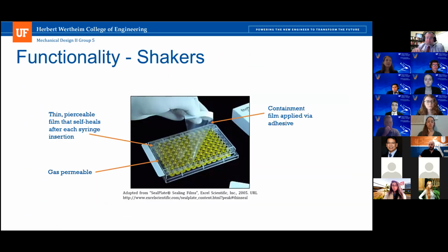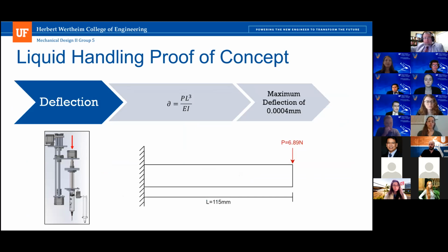But because it's attached to our liquid handling system, yes, this bottom one on the left here. The arm itself can be seen in the bottom right portion of that image. And so in this position, it is in the measurement mode. It is the lowest point of our liquid handling system and can move up and down with that system to accommodate the different well plate heights or the different tube heights. For example, if you have a tube filled halfway with medium, it would not be advisable to take a measurement at the top of the tube.